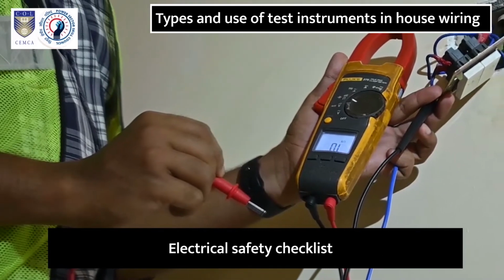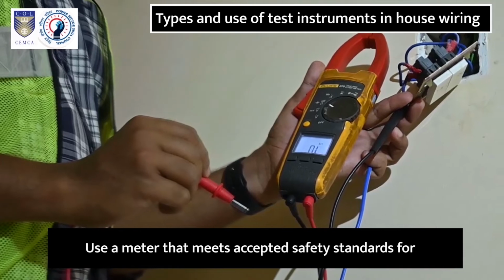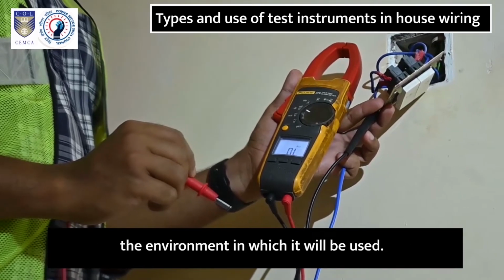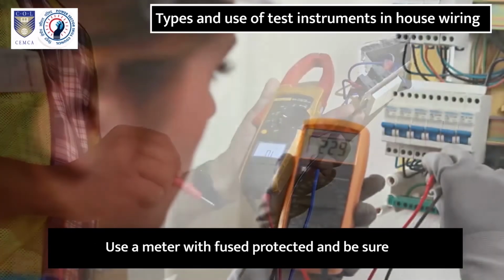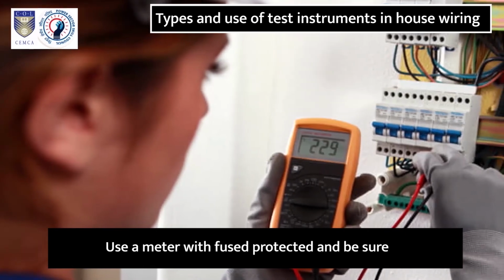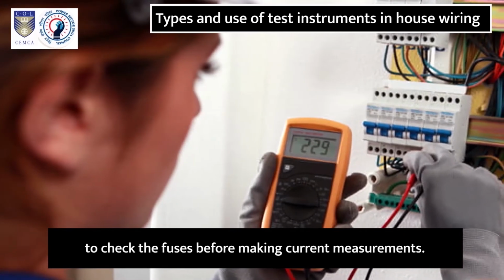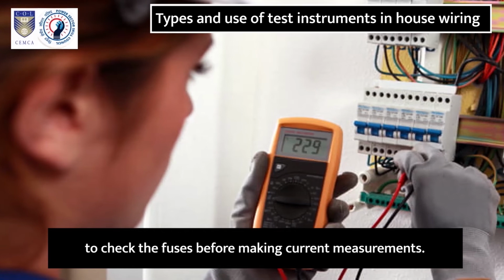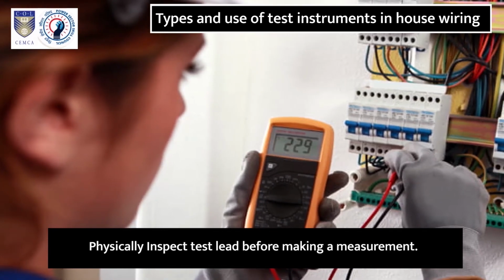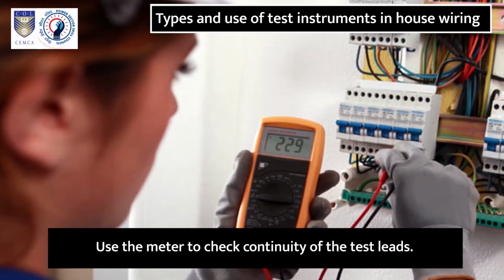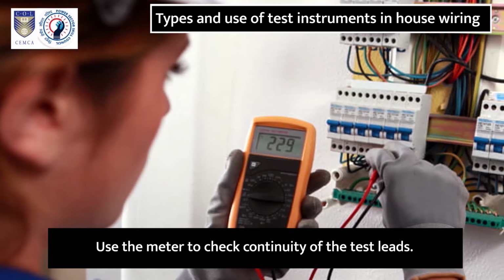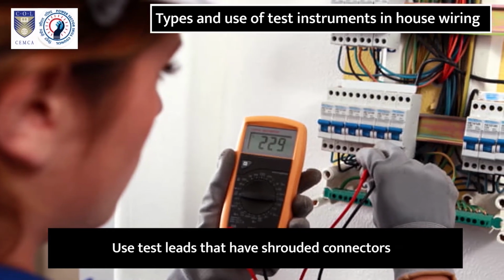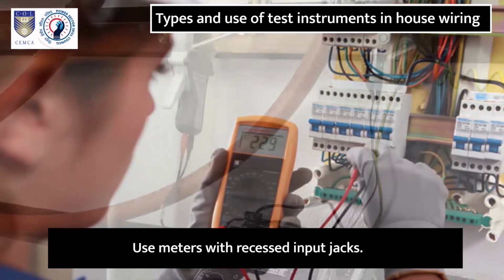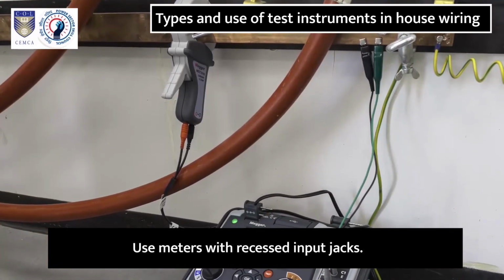Electrical safety checklist. Use a meter that meets accepted safety standards for the environment in which it will be used. Use a meter with fuse protection and be sure to check the fuses before making current measurements. Physically inspect test leads before making a measurement. Use the meter to check continuity of the test leads. Use test leads that have shrouded connectors and finger guards. Use meters with recessed input jacks.